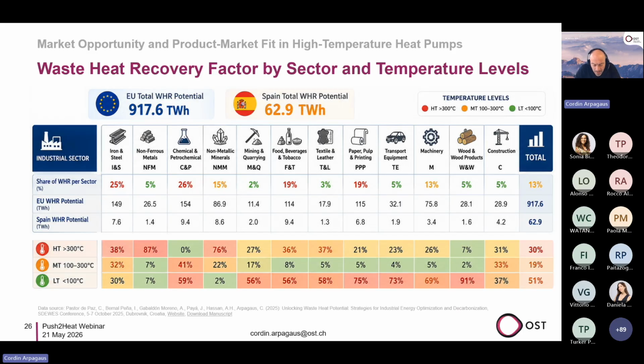And another aspect is the waste heat. So here we have a table that we developed also in the Push to Heat project that shows the waste heat recovery factor by the sector and temperature levels. It's a lot on this slide, but we can see that, for example, in Spain, we have 62 terawatt hours of waste heat, and this can then be distributed in different temperature levels. And we see below 100-degree waste heat, the lowest line there, we see high potential pulp and paper. In the middle of the slide, 75%. So it seems that this sector offers high waste heat recovery potential, and also at the temperature level that is suitable for heat pumps. So this waste heat recovery analysis is also part of the game to find a good product market fit.